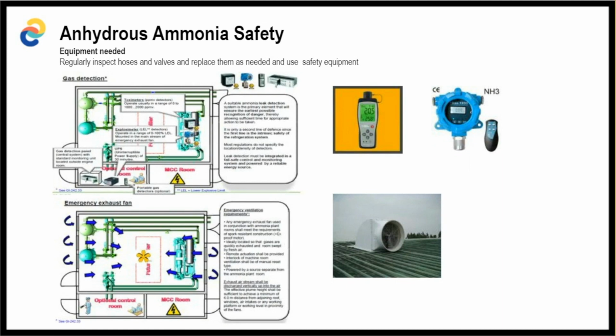At least one ammonia detector, as best practice, shall be provided in the room or area. Alarms shall be activated whenever the refrigerant vapor exceeds the permissible exposure limit, which for people is normally around 50 ppm. Audible and visual alarms shall be provided inside the room to warn when the alarm has activated. Access to the room is restricted to authorized personnel and emergency responders only. In connection with the leak detector, purge fans shall also respond automatically to the refrigerant concentration detection system.